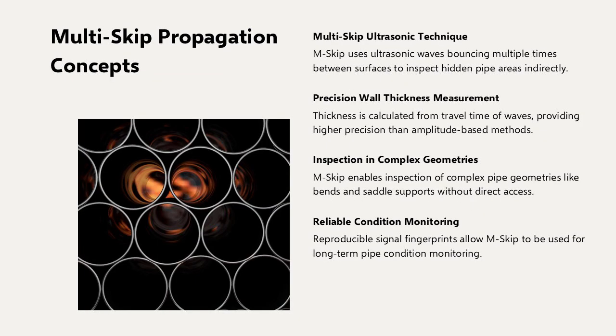Multi-skip ultrasonics, M-skip, expands on the wave-skipping behavior observed in creeping and head wave modes by enabling ultrasonic energy to bounce multiple times between internal and external surfaces. This pitch-catch technique places probes on opposite sides of obstructions, allowing indirect examination of hidden pipe surfaces. The wave reflections create predictable travel paths, and the measured arrival times provide accurate wall thickness data. M-skip is valuable for circumferential and axial inspections, even in complex geometries such as pipe-to-bend transitions and saddle supports.